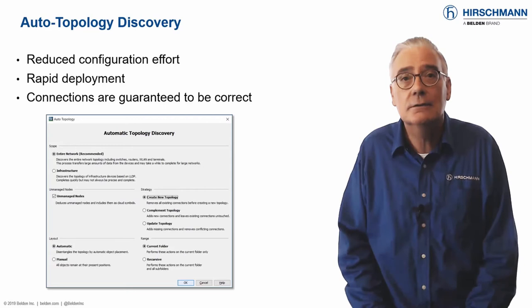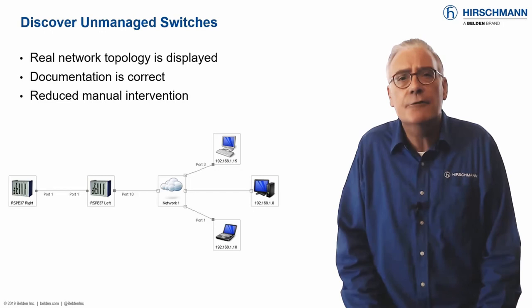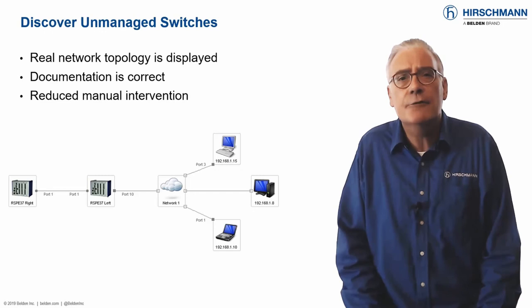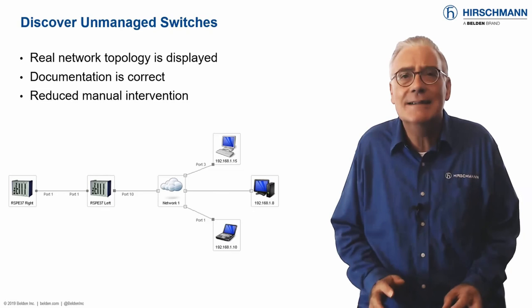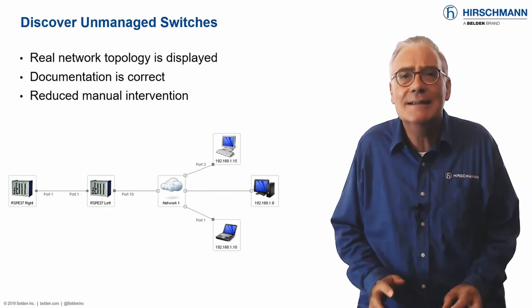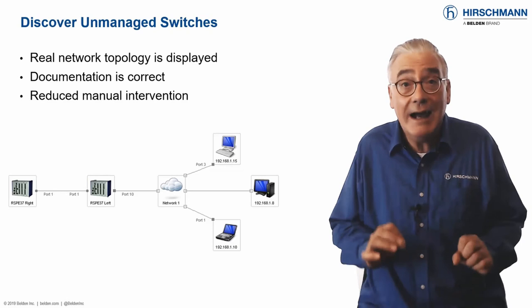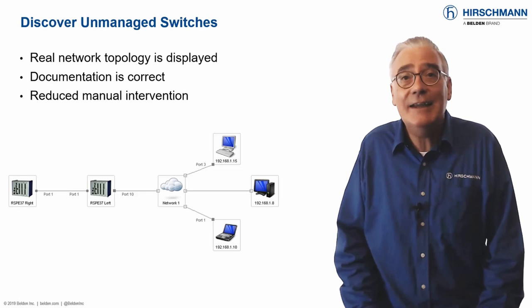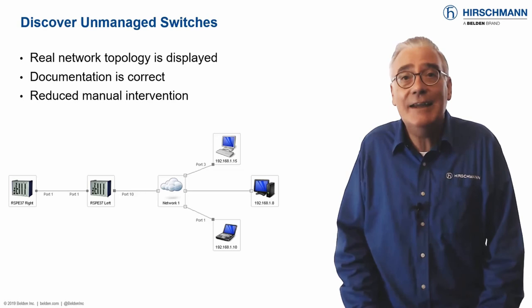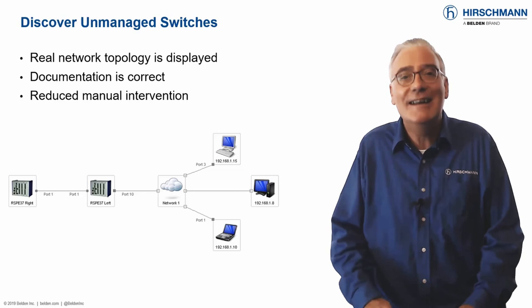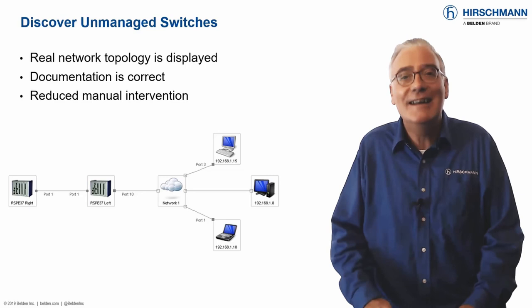To reliably supervise a network, the infrastructure must be built using managed switches. These devices provide information about topology and status, which forms the basis of the graphical display. Managed switches are slightly more expensive than unmanaged ones. For this reason, some users deploy unmanaged switches at the edges of a network where the operation is not critical. Even so, it is still important to have an accurate overview of your complete network topology. You could manually draw the unmanaged switches in your network map, or you can allow Industrial HiVision to deduce the location of unmanaged switches and display them as part of the topology map.